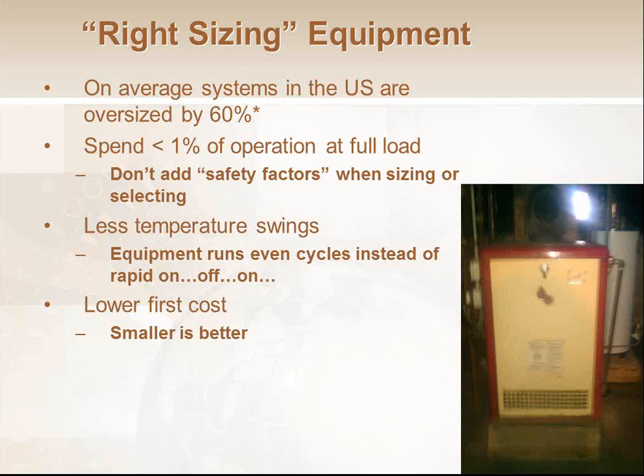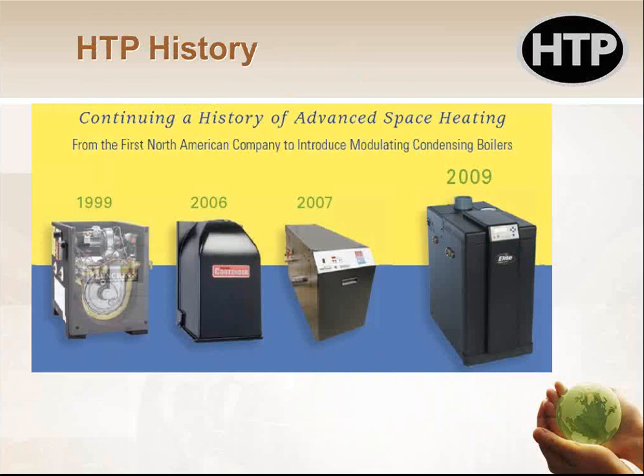If you're just swapping out a like-for-like item, most municipalities have not been asking for the load calcs. They've just been saying, okay, it's like-for-like, we're just going to let it slide, even though the code technically would require you to do the load calc. So you need to be prepared to do it. You probably should just do it anyway so you can size the boiler correctly and kind of go from there.